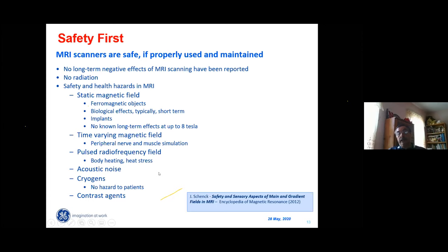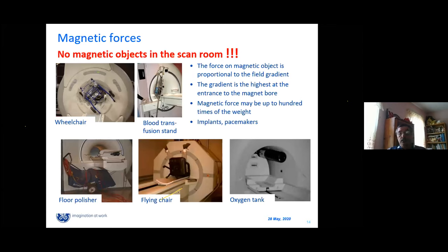Acoustic noise caused not by magnet, but mainly by gradient coils. And our experience is as soon as we are able to reduce the noise of MRI scanner, physicians want to increase strength of the gradients or strength of magnetic field. So they use noise reduction to get better image quality and higher throughput. Not that much about patient comfort. And the last but not least, contrast agents. We're trying to minimize the use of contrast agents. Here you see some effects. What you see is mainly effects on janitors. Janitors, when they clean the room, you don't feel magnetic field at all up to a certain point when it's too late. So no magnetic objects inside the scan room.